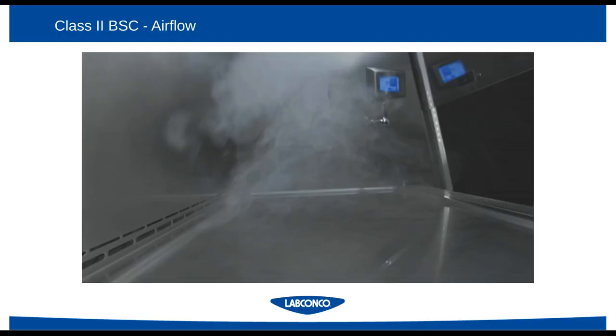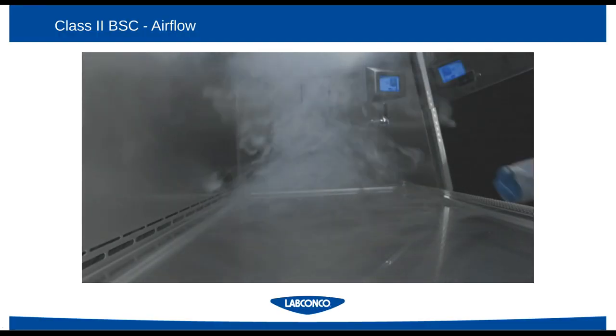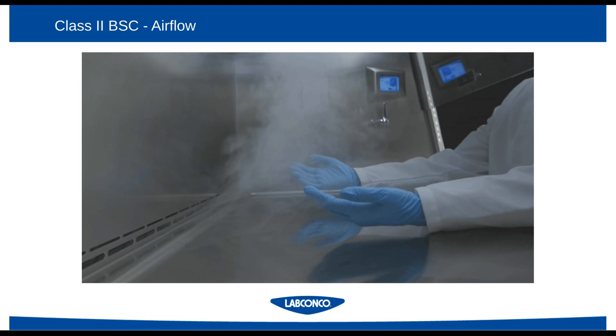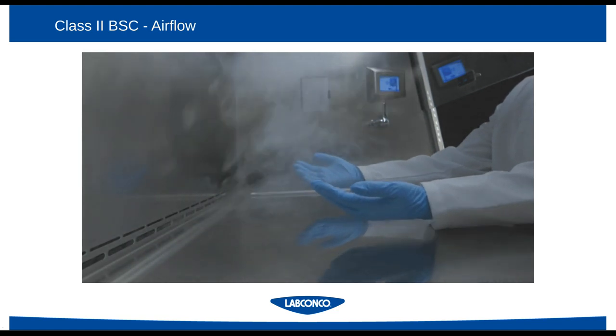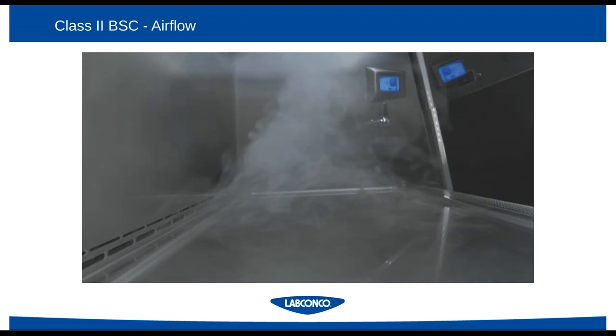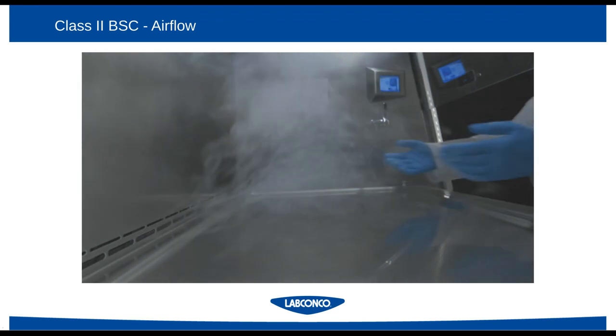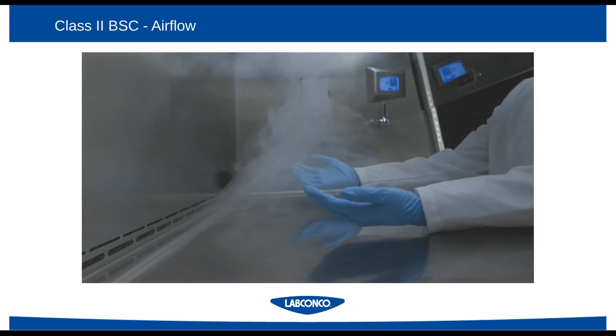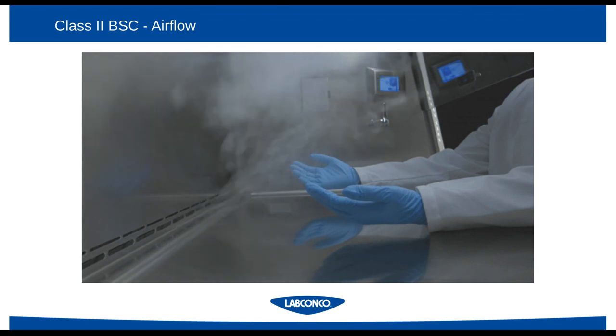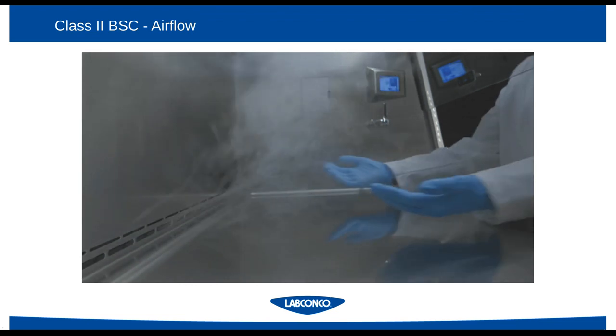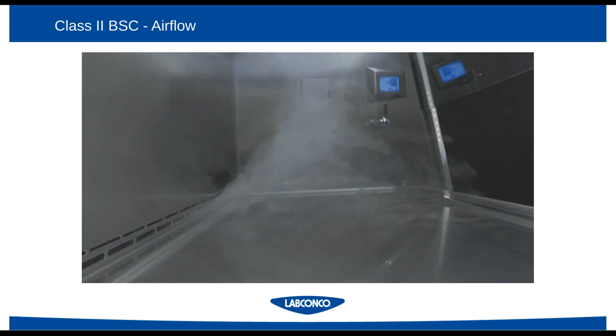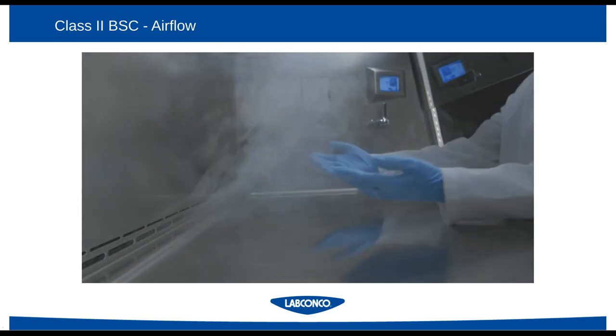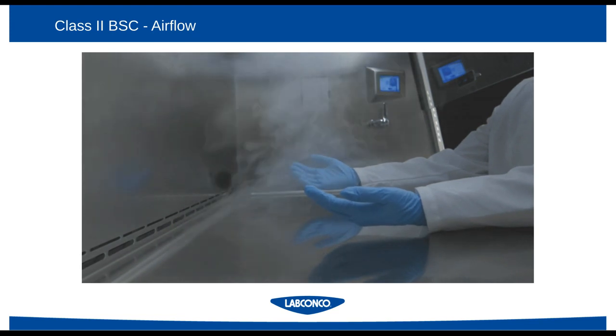If we visualize airflow within the enclosure, you can see on this slide, you may have to click play if it's not already playing, the downflow smoke within the cabinet. This is representative of unidirectional air, or sometimes laminar air, and it represents a clean, straightforward path of airflow downward in the cabinet. This is the principle that helps keep things clean as it comes out of the HEPA filter. It also helps to ensure limited or no cross-contamination as the airflow sweeps contaminants and pulls them into the air vents at the front and back of the hood.